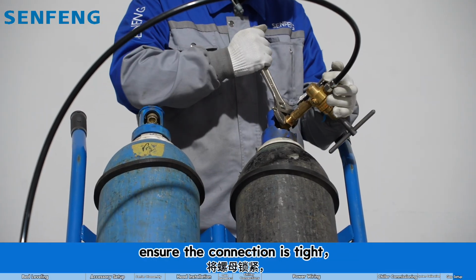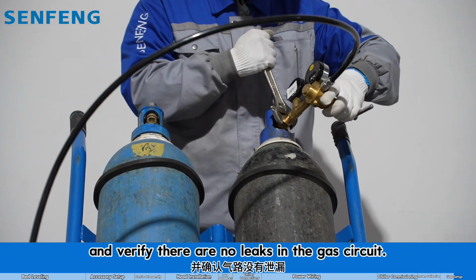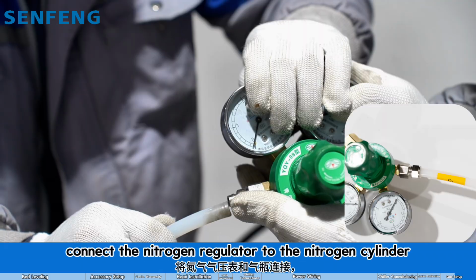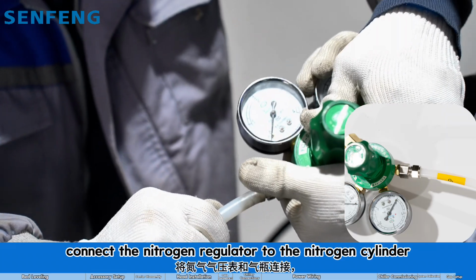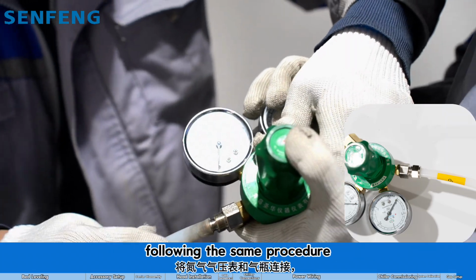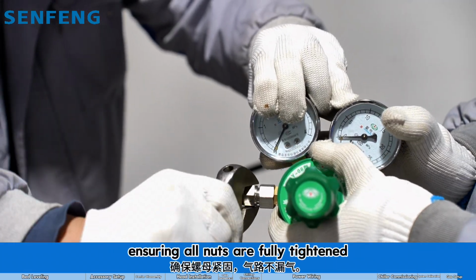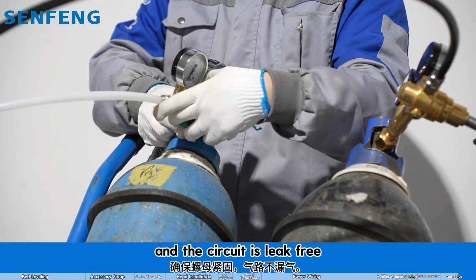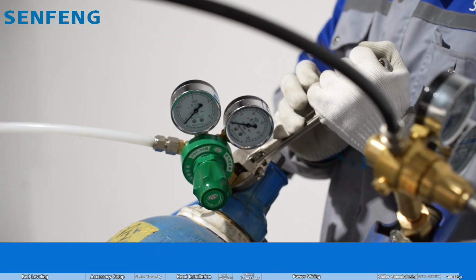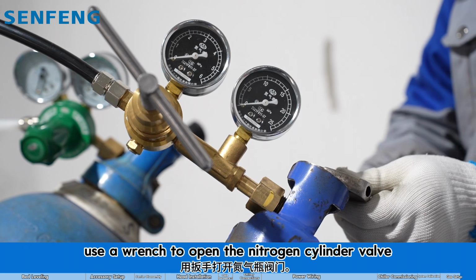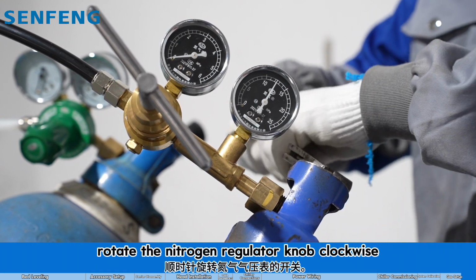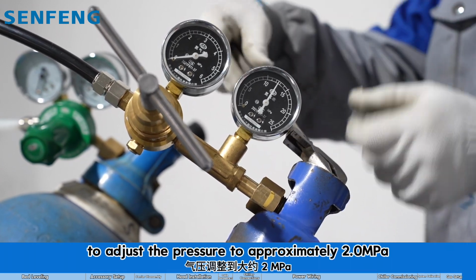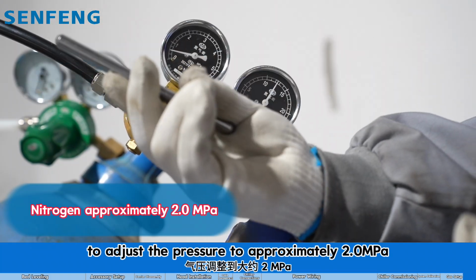Ensure the connection is tight and verify there are no leaks in the gas circuit. Connect the nitrogen regulator to the nitrogen cylinder following the same procedure, ensuring all nuts are fully tightened and the circuit is leak-free. Use a wrench to open the nitrogen cylinder valve. Rotate the nitrogen regulator knob clockwise to adjust the pressure to approximately 2 megapascal.